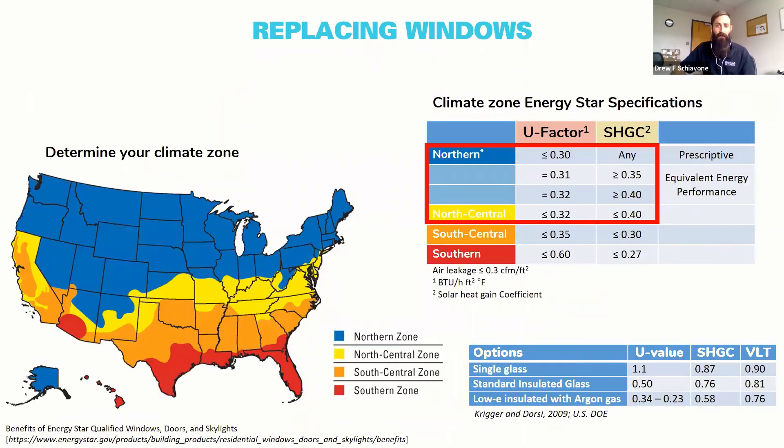Recommended values are based on climate zones. Most of Maryland falls in the north-central yellow region, though Garrett County and western Maryland have different factors. Recommendations here call for a solar heat gain coefficient at least 0.40 and a U-factor of 0.32 or less. The air leakage rate should be 0.3 cubic feet per minute or less. You can check these values when looking to purchase windows.